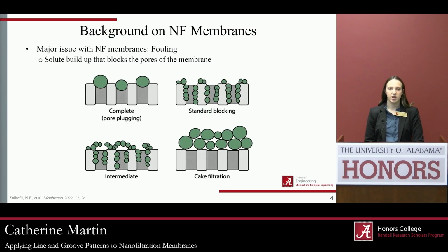One major issue with nanofiltration membranes is fouling on the surface of the membrane. Fouling is buildup of solute on the membrane surface, which blocks the pores of the membrane, leading to a decrease of permeance and rejection of the membrane over time.